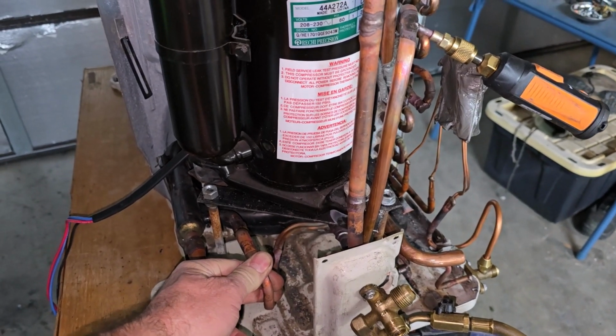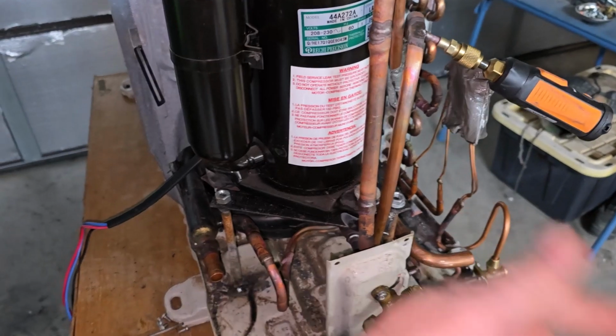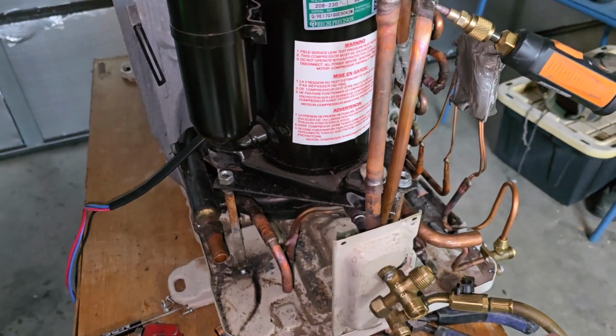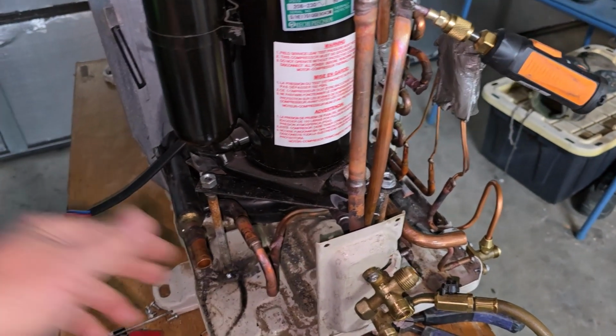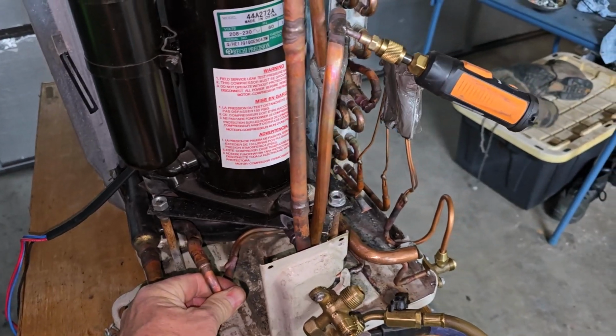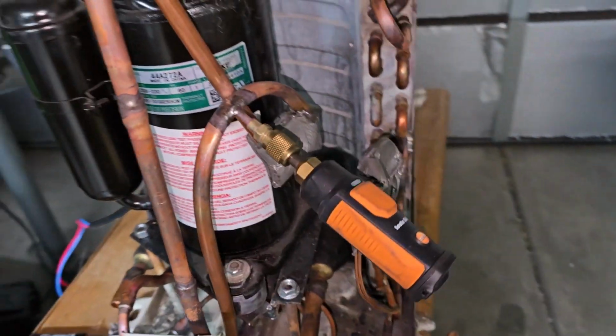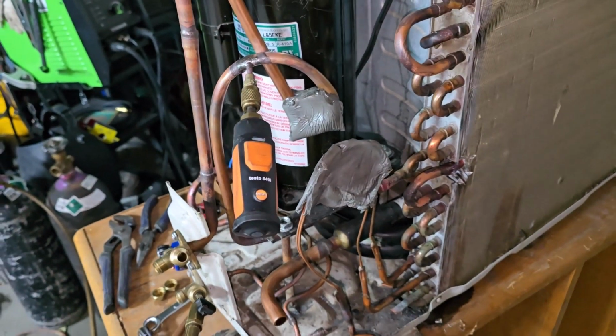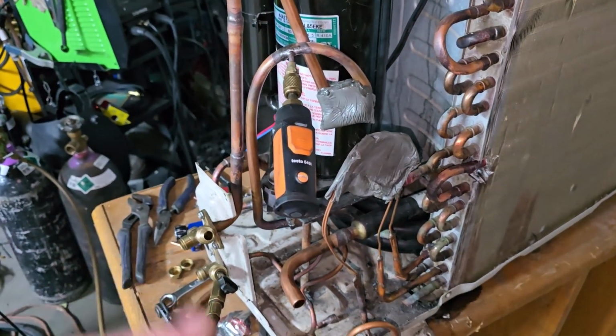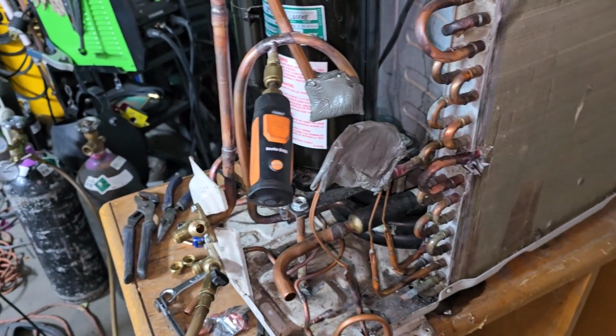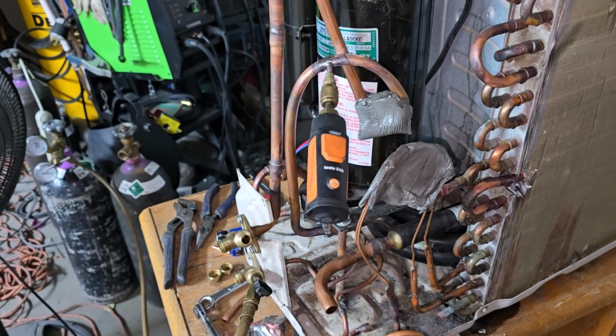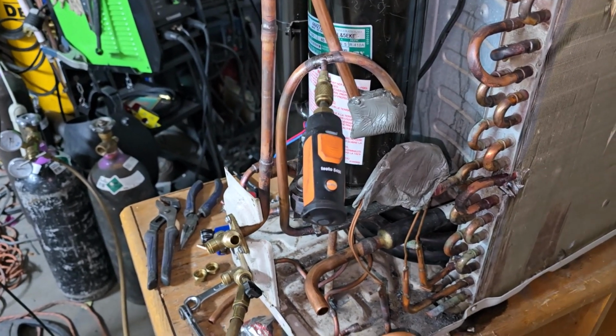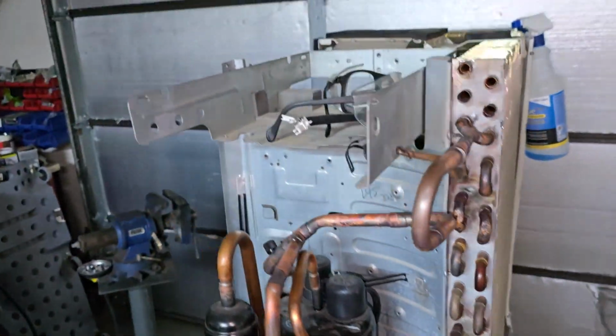Basing the pump on and off, and then the speed of the pump for the circulated pump to the water heater, based on liquid line, has been working pretty good for me on the other unit, which always regulates the output of the water temperature to always be like, usually shoots out at least 130 degree water into the top of the tank, so it comes out pretty good.